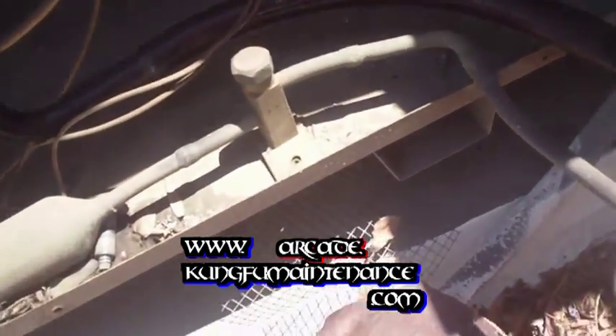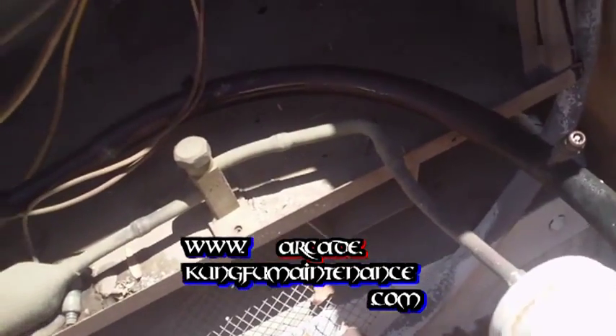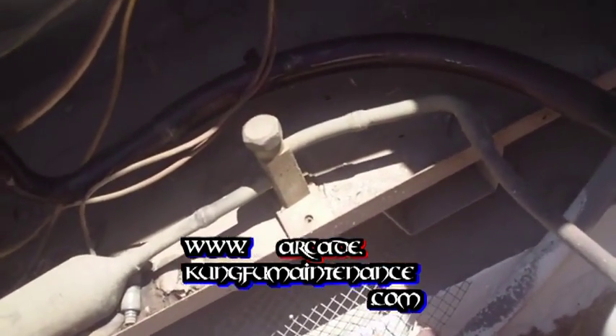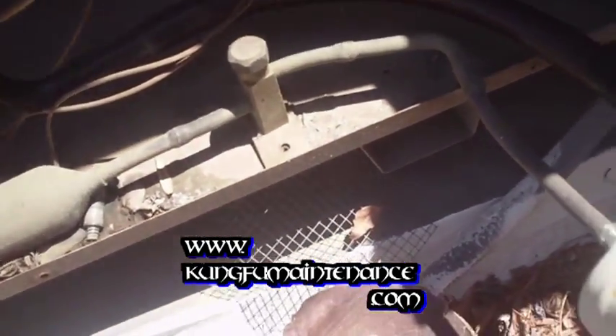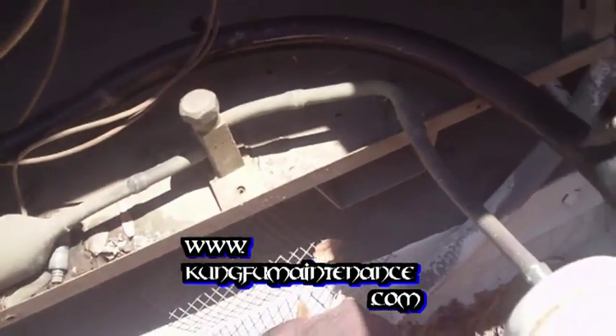The second most common place is in the evaporator coil, because of the conditions the evaporator runs in — it's always moist. With copper and metal, all the conditions that work for rust and developing a leak, you'll see a lot of rust a lot of times on the evaporator coil.